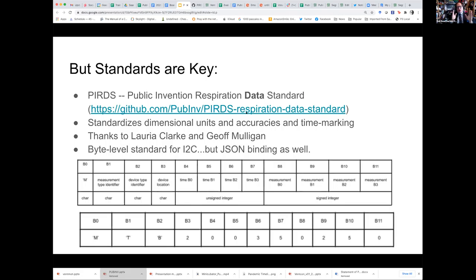Doctors, even in Guatemala, have said they don't want to use a ventilator unless it shows them a respiration trace of what's going on in the patient, because doctors can make all kinds of informed analysis. Normally, that's a pressure curve and a flow curve, but there are some other things in that.